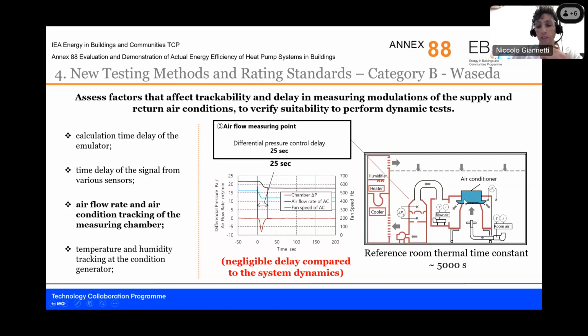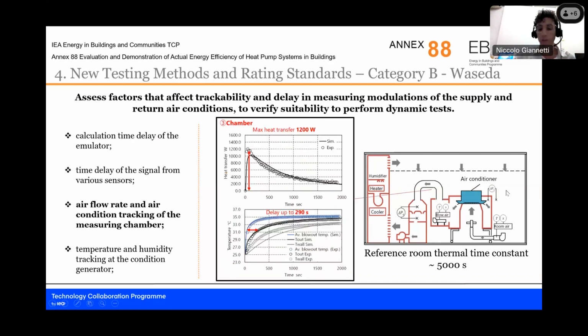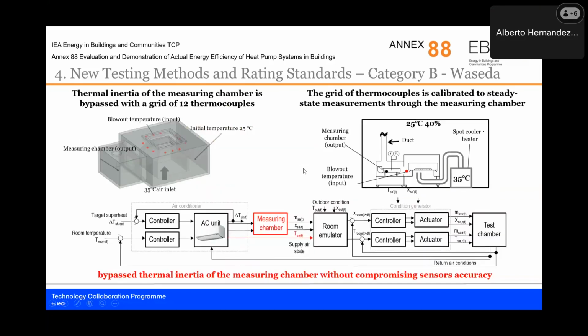Then the trackability of the air condition at the supply port. So the volumetric flow rate of the air needs to be measured for the cooling capacity, as well as temperature and humidity measured after collecting the air flux from the indoor unit. This delay was bypassed by using a thermal grid of thermocouples calibrated to the PT sensor to maintain accuracy and bypass the delay of the chamber itself.